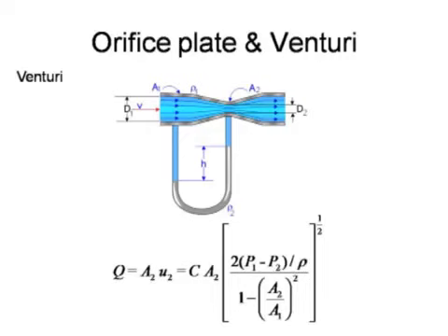And of course it's the same flow rate at position 1 as position 2. That's our continuity equation again, that what goes in comes out. On the right hand side of the equation, apart from the rearrangement, we've also added a discharge coefficient, illustrated here as being capital C, sometimes CD. And that really is something to take into account some of the energy losses in our system. So for an orifice plate that might be 0.6, 0.7, whereas in a venturi maybe 0.9, 0.96, something of that sort of order.